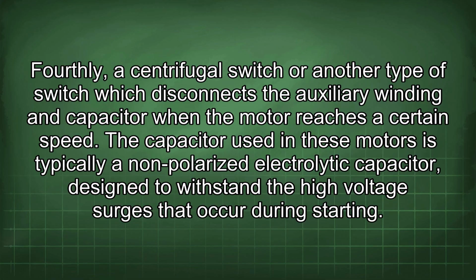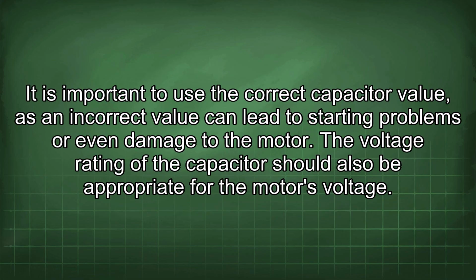The capacitor used in these motors is typically a non-polarized electrolytic capacitor designed to withstand the high voltage surges that occur during starting. It is important to use the correct capacitor value, as an incorrect value can lead to starting problems or even damage to the motor. The voltage rating of the capacitor should also be appropriate for the motor's voltage.